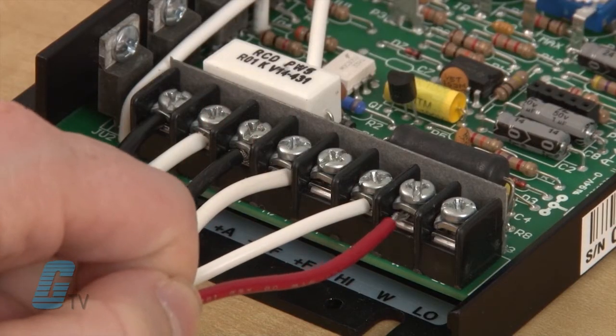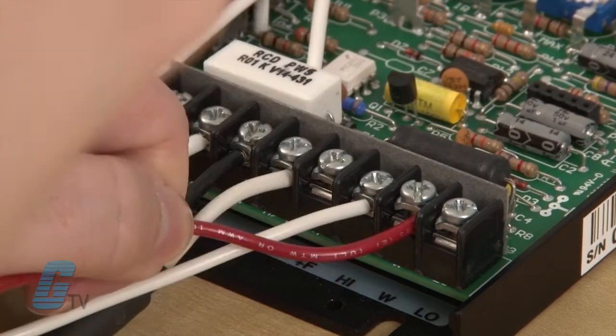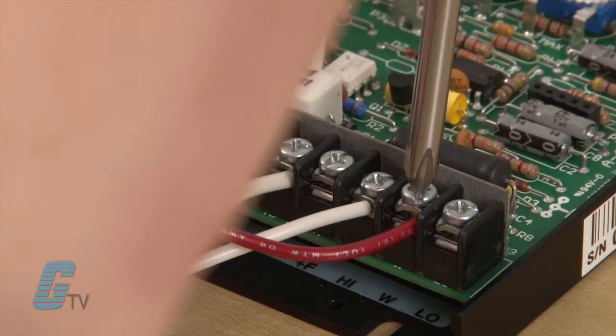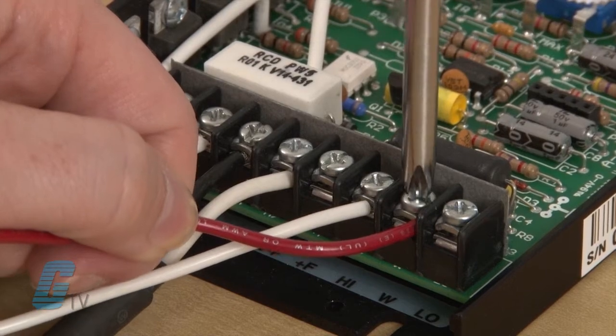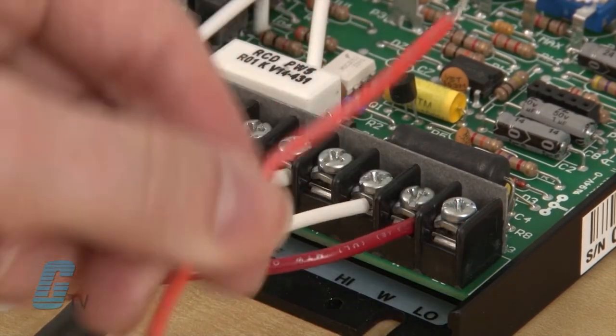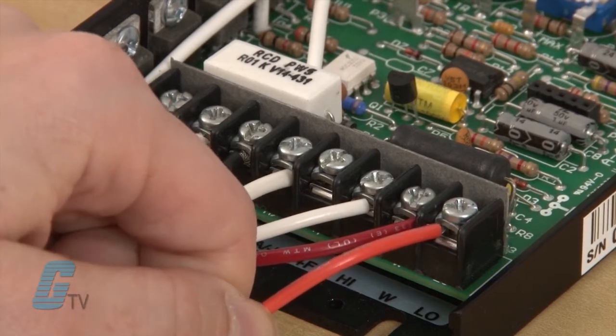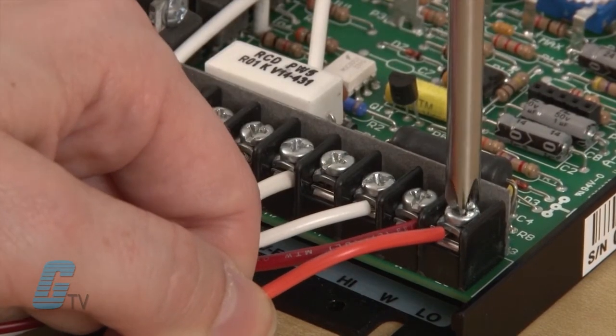The seventh terminal has a red wire that connects to the speed pot's wiper. If using for voltage follower applications, this input should not be greater than 12 volts or grounded. My last terminal is an orange wire that connects to the low side of the speed pot.